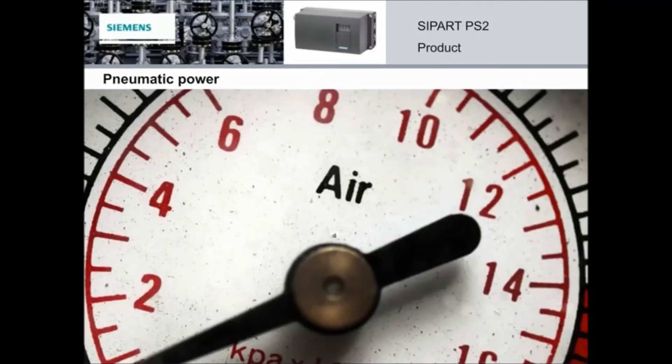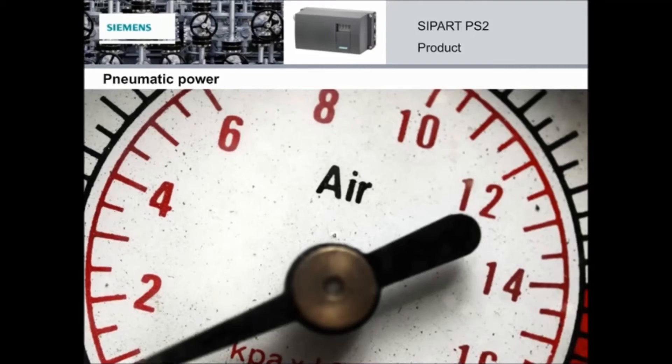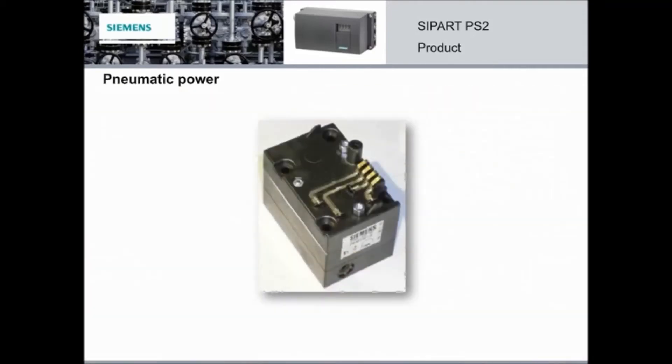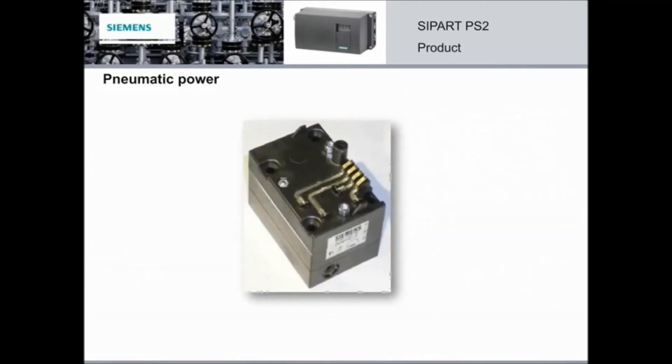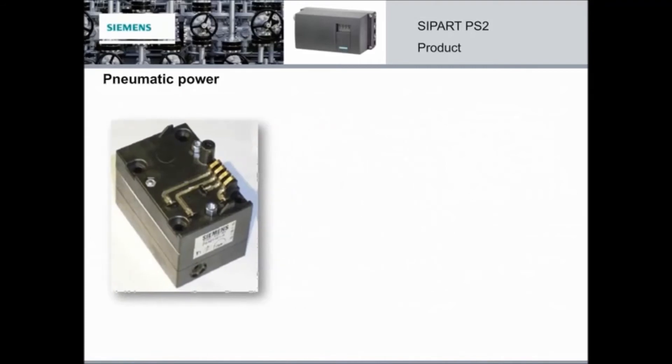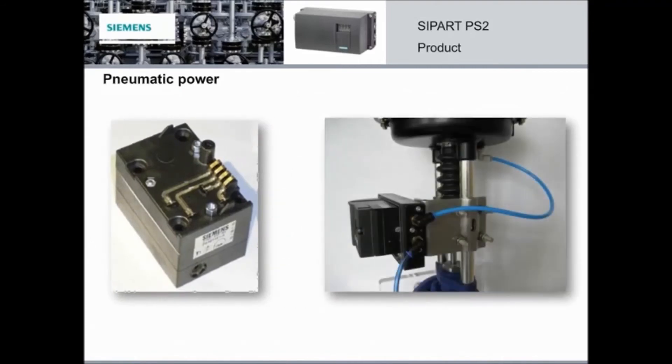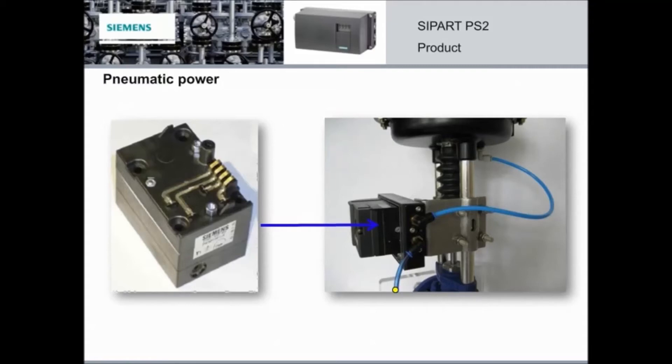The SIPART PS2 is an electro-pneumatic positioner because it controls pneumatic actuators which move valves with compressed air. This is the pneumatic block inside the PS2 that changes the air flow. It uses special piezo-crystal technology. The piezo valves are only activated when there's movement, so there's minimal air consumption. The compressed air comes in, and the pneumatic block in the positioner changes the air flow going to the actuator, which then moves the valve.